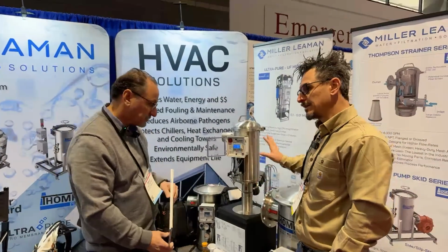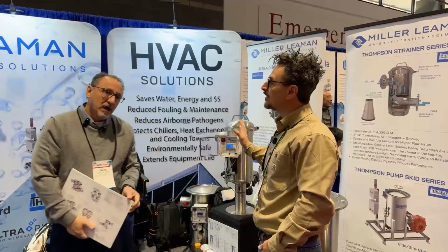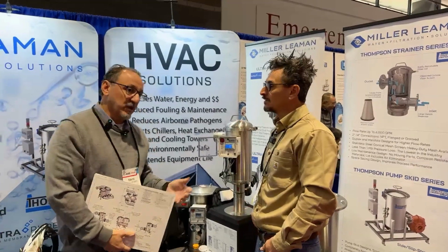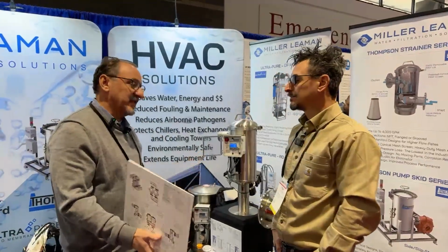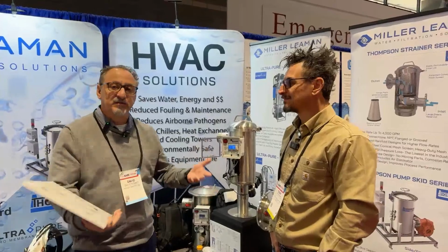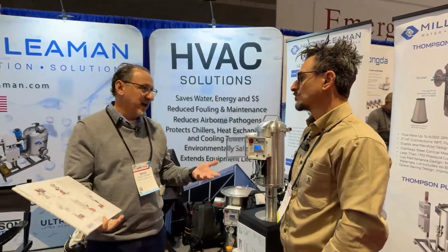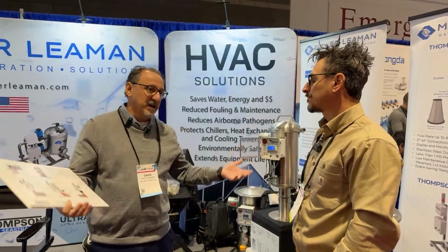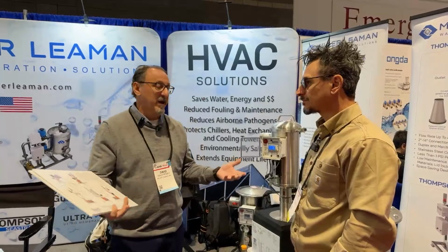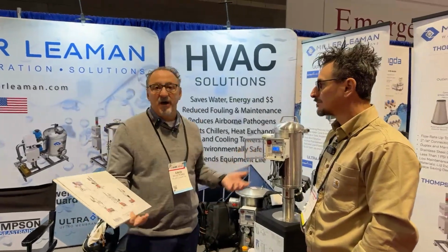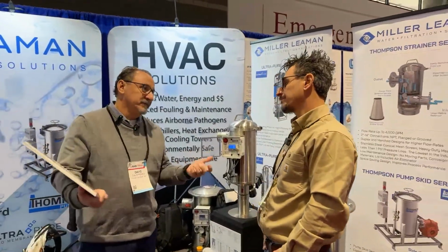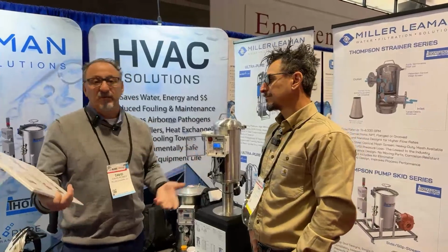So do you typically see this on the tower side or on the primary chilled water side? The chilled water side, right. We have seen them on the cooling tower side. It really all depends on how many tons your cooling tower is. If you have an 800 ton and you're flowing 2,400 GPM, why not put a 12-inch strainer right on it and filter 100% of your water? If you have a 3,000 ton cooling tower, it's a little bit more challenging.